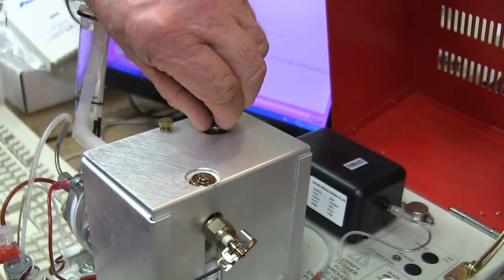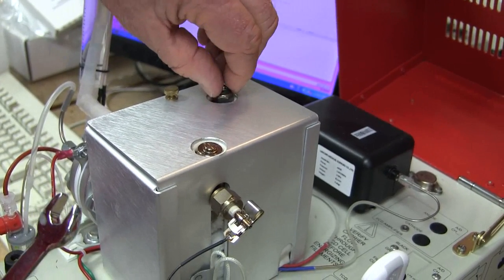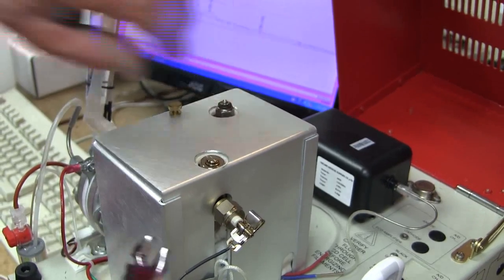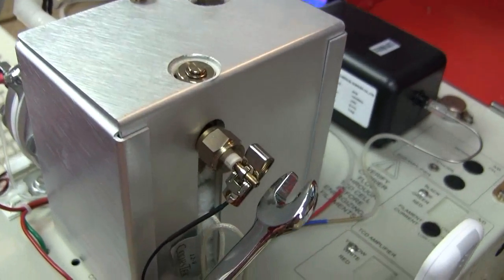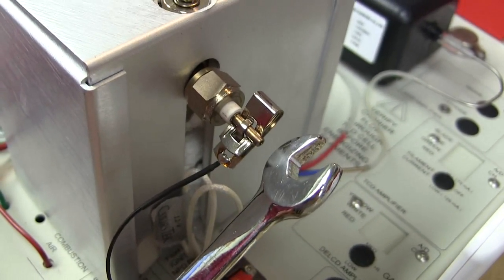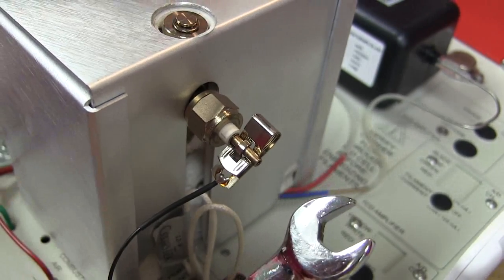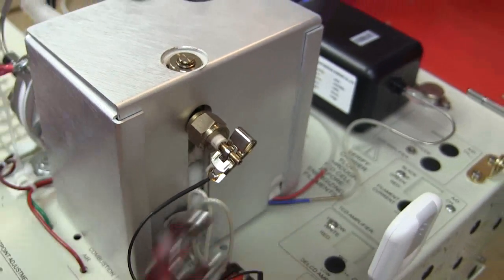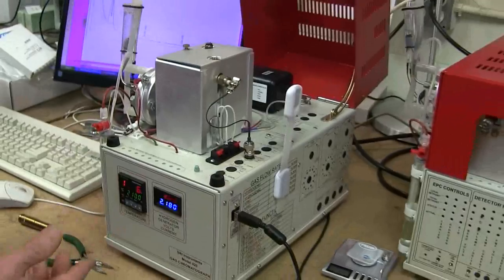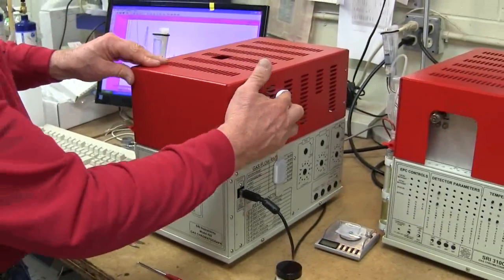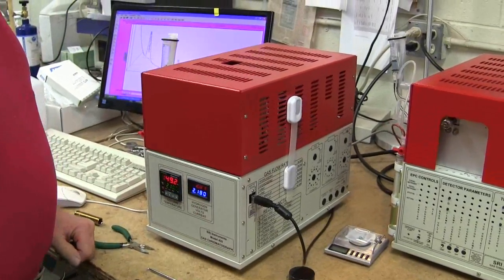So it's not good to over-tighten the septum. It's kind of adjustable a little bit one way or a little bit the other way. But if you over-tighten the septum, it won't last as long as if you get it just perfect, which is kind of just tight enough. So thank you, that's really the only maintenance item on the GC, and thank you for your patience.